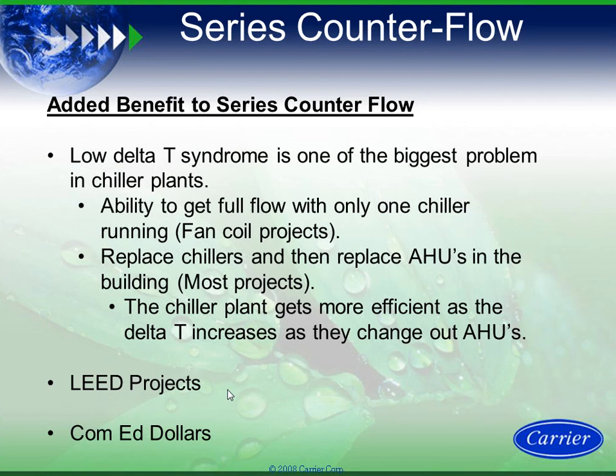With the 23XRV in series counterflow, I have two machines in series. I'm able to run one machine at, say, 50% load, and actually run more flow through it if I needed to have more flow. Again, it's a Band-Aid. It doesn't fix the problem. It's a Band-Aid if you have low delta T syndrome. It prevents me from turning on a second chiller.